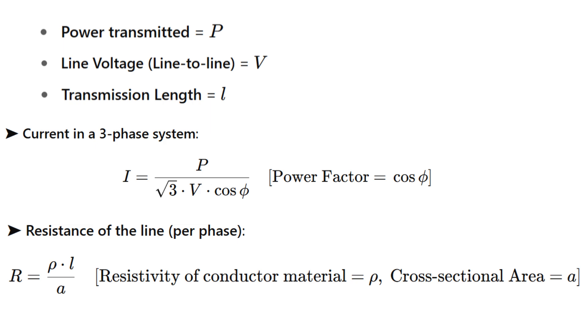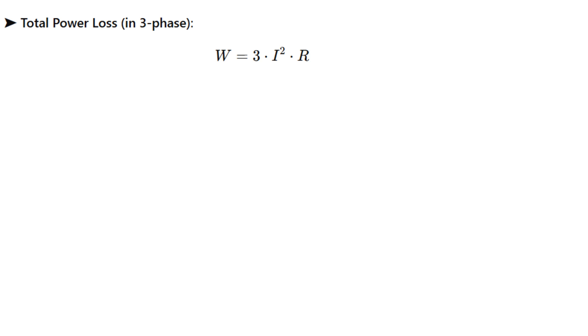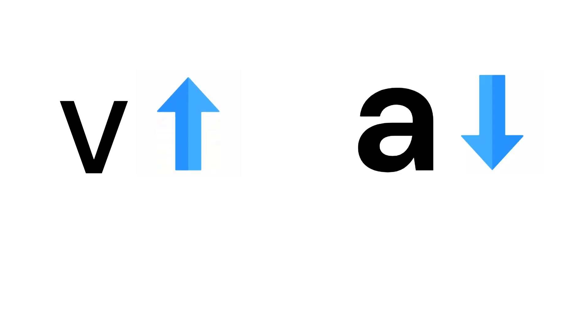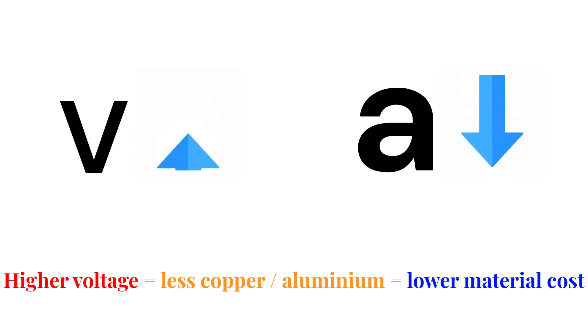And resistance of the conductor R is given by rho into L by A, where rho is the resistivity and A is the cross-sectional area. Now the total power loss W equals 3 times I squared R. Substituting the values, we get power loss as P squared rho L divided by V squared into cos phi squared into area A. From here we find that the area A is directly proportional to P squared rho L divided by power loss into V squared into cos phi squared. That means when voltage V increases, the required cross-section area of conductor decreases drastically. As a result, the total volume of conductor material goes down. Simple takeaway: higher voltage equals less copper or aluminum, which equals lower material cost.